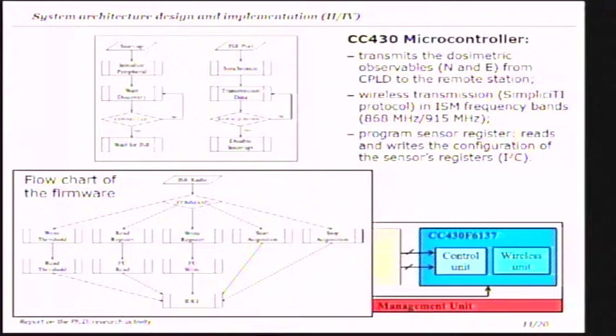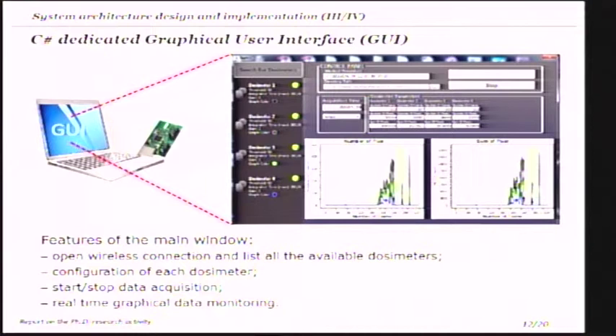The microcontroller firmware receives these two observables and sends them wirelessly to a remote station. The wireless protocol is the SimpliciTI protocol, and the microcontroller can work in two frequency bands: the European band and the American frequency band. A dedicated acquisition system has been designed that controls the data acquired by the system. The user can list the available dosimeters on the network, control the start and stop of acquisition, and two graphs monitor in real-time the data recorded by each dosimeter.